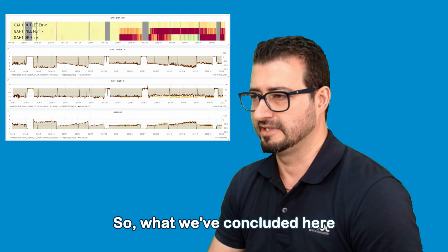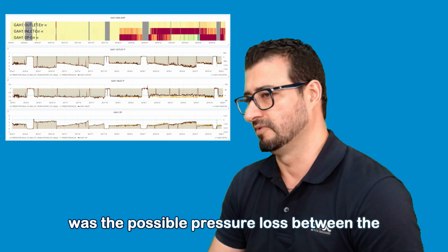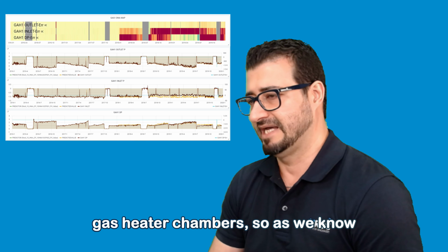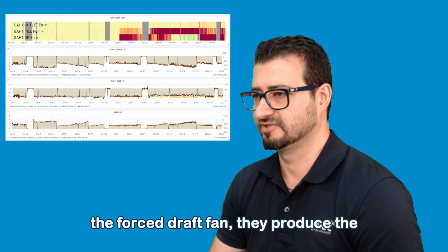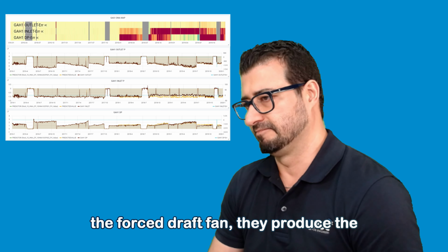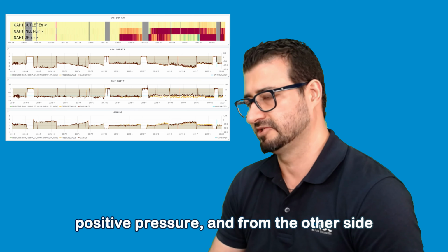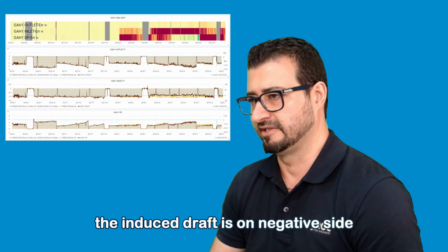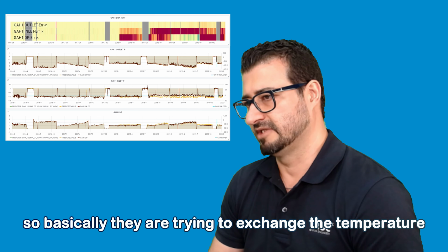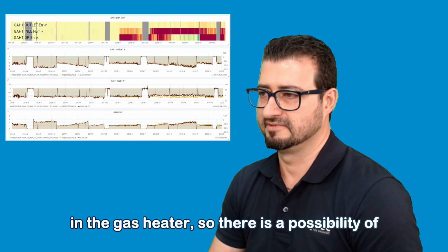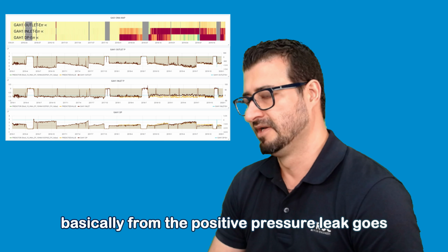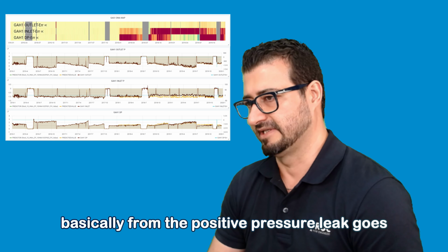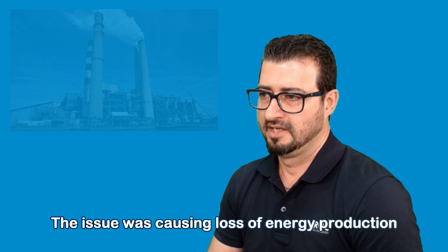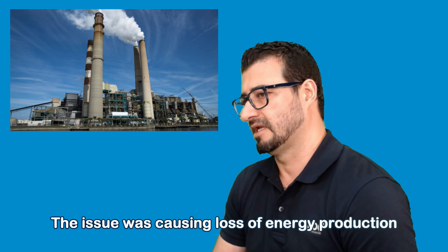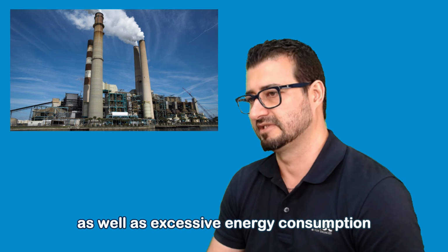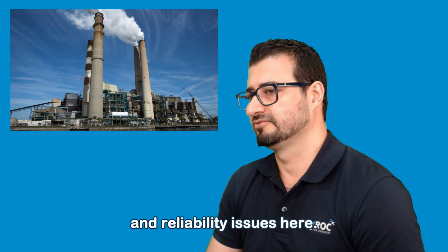So what we concluded here was a possible pressure loss between the gas heater chambers. As we know, the forced draft fan produces the positive pressure, and on the other side the induced draft is on the negative side. So they're trying to exchange the temperature in the gas heater, so there is a possibility that the positive pressure leaks towards the negative pressure, as we see here. The issue was causing loss of energy production as well as excessive energy consumption and reliability issues.